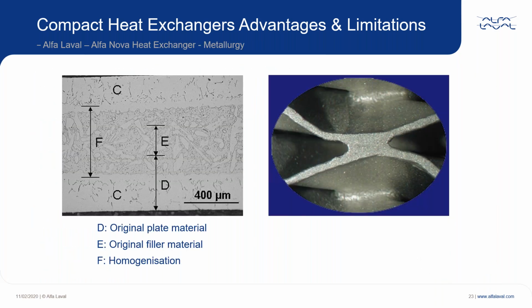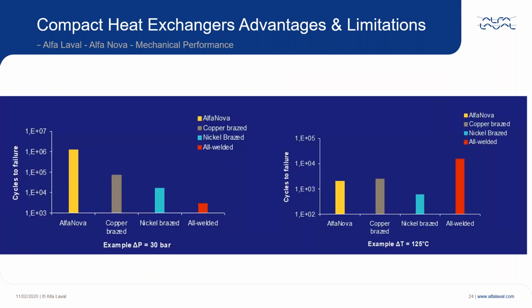It's just a graphic there showing that when we go through the fusion process, there is a high degree of homogenization in the plate. And the reason this was developed was, see, copper can't be used with lots of fluids, so nickel brazed units were weaker. With the AlfaNova, this gives you a comparison of the fatigue cycling, both pressure and temperature. And generally the AlfaNova comes out quite positive.